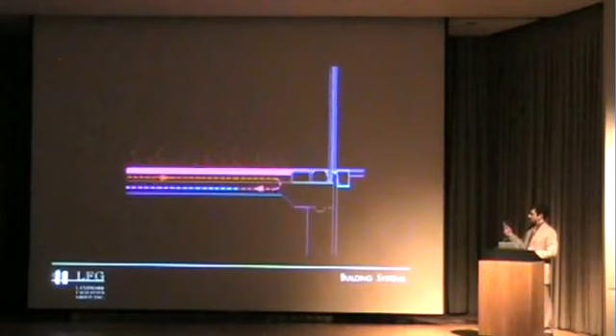And I'd like to start with the radiant floor that Toshiko talked about before. In the wintertime, we have a radiant heating system installed below the slab that takes care of the primary heating load for the building. It adds to the occupant comfort. It helps reduce the amount of airflow we need to only accommodate building pressurization and code-required ventilation from outdoors. And by reducing that, we can reduce our fan speed a lot and increase our energy efficiency.